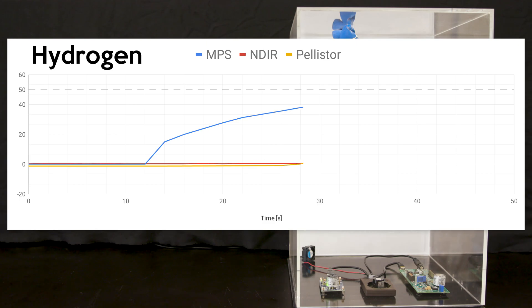the CAT bead under-reports the concentration, and the NDIR is incapable of even seeing hydrogen, and so reports zero.